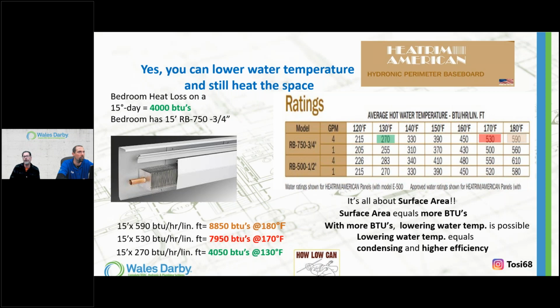How low can you go? It says right here, it's all about surface area. Surface area equals more BTUs. With more BTUs, lowering water temperature is possible. Lower water temperature equals condensing and high efficiency. Marry the emitter back to the source, marry the source output to what the envelope really requires.